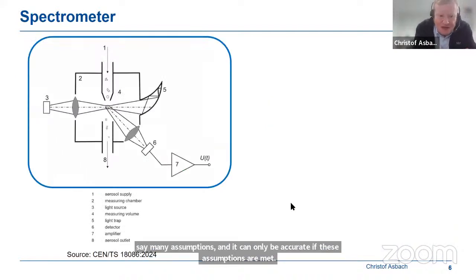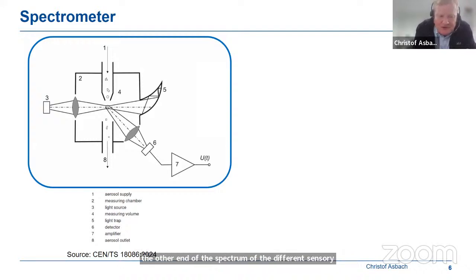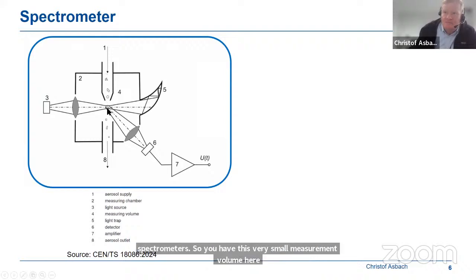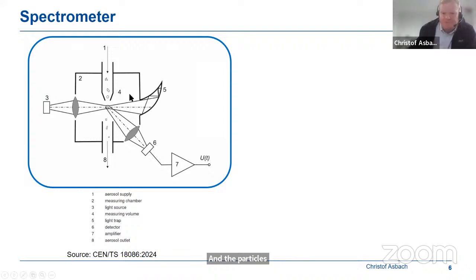On the other end of the spectrum of the different sensor working principles is the spectrometer. In fact, this is also a very common device of scientific grade instruments, where you have single particle counters or single particle spectrometers. So you have a very small measurement volume here, and the particles are transported through this measurement volume in such a way that ideally, at most, a single particle is present inside the measurement volume.